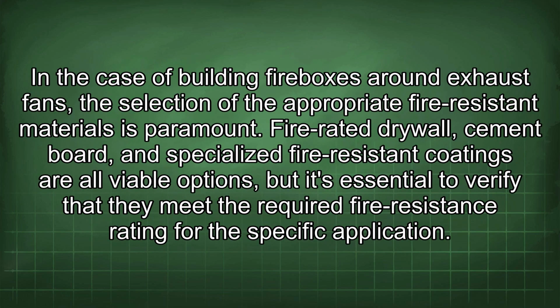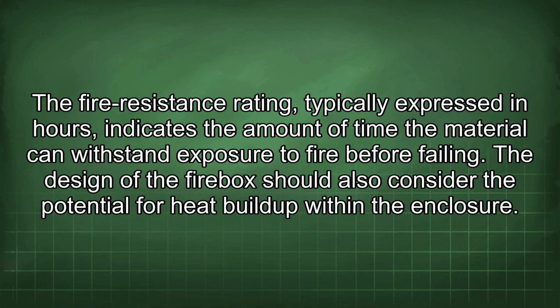In the case of building fireboxes around exhaust fans, the selection of the appropriate fire-resistant materials is paramount. Fire-rated drywall, cement board, and specialized fire-resistant coatings are all viable options, but it's essential to verify that they meet the required fire resistance rating for the specific application. The fire resistance rating, typically expressed in hours, indicates the amount of time the material can withstand exposure to fire before failing. The design of the firebox should also consider the potential for heat buildup within the enclosure.